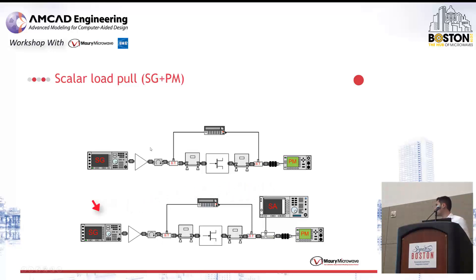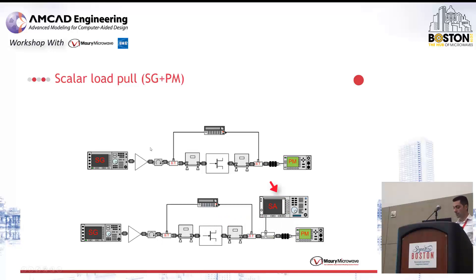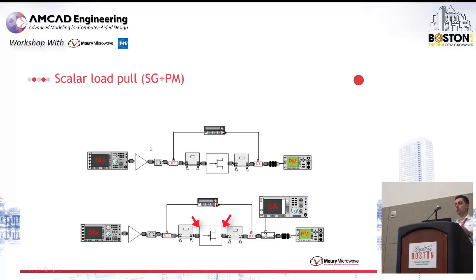You have signal generators and amplifiers for generating your test signal. You might have couplers at the input to measure power or spectrum. You have a source tuner, a device under test, and a load tuner. Then you have a power meter to measure power, or a spectrum analyzer if you want to do linearity measurements. A very important thing about this type of system is that since you're measuring power at this point, you need to know exactly what your tuner is doing. You need an accurate representation of your tuner to de-embed your measurements up to the device reference plane. This whole structure is based on the pre-characterization of the tuner measured offline with a vector network analyzer.